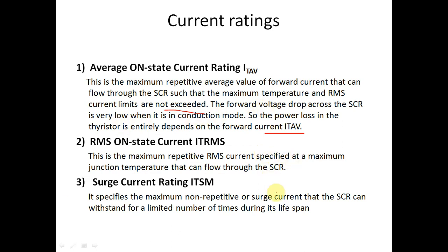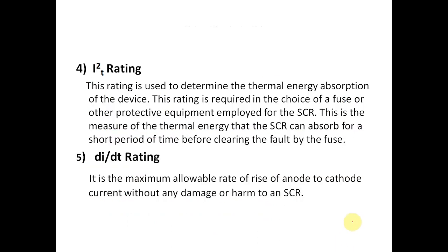Surge current rating specifies the maximum non-repetitive current. This current is allowed a limited number of times during its lifespan. I square T rating is used to determine the thermal energy absorption. Thermal energy is nothing but if your SCR device is turned on for some duration, it will dissipate heat. And due to turning on the SCR for more time, the SCR will be damaged or fault.